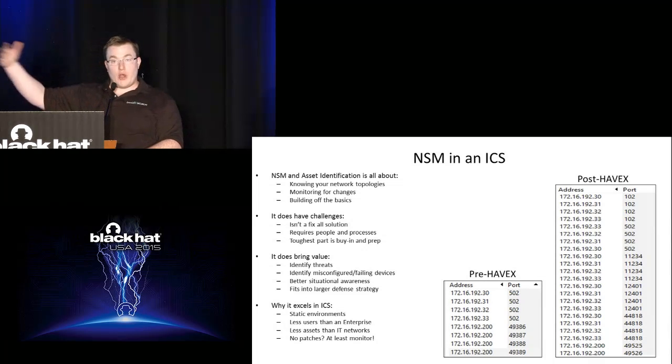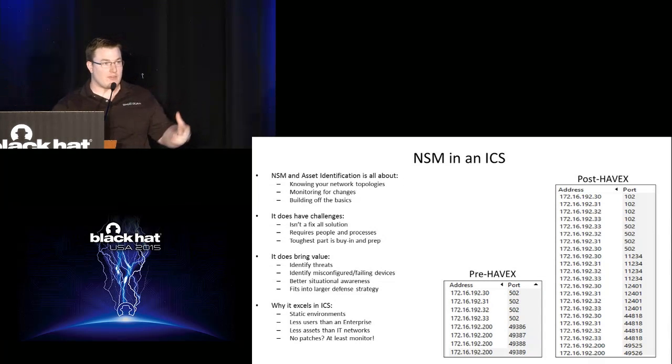And so when we look at the post-Havex infection of this network, here are all these ports and protocols, and all these IP addresses that aren't normal in our environment. If I only use Modbus TCP or 502 inside my environment, there's no reason for me to see ISO TSAP and 102 and these different ports being accessed. And that should instantly be a red alarm for anybody in these environments. It can really be that simple.